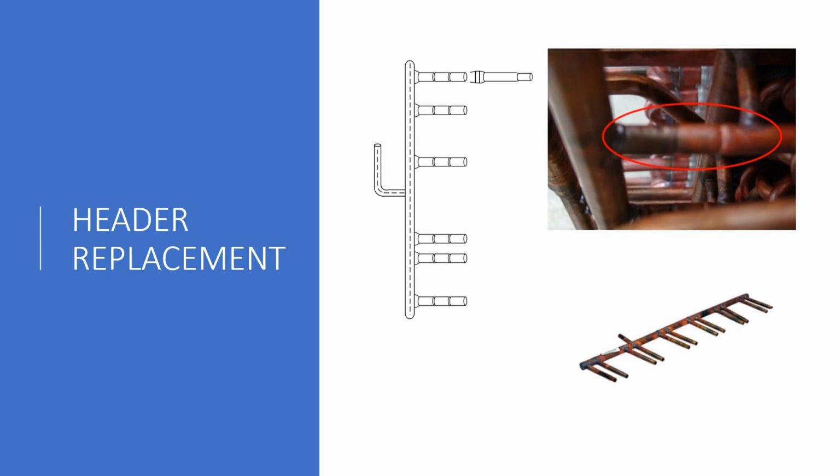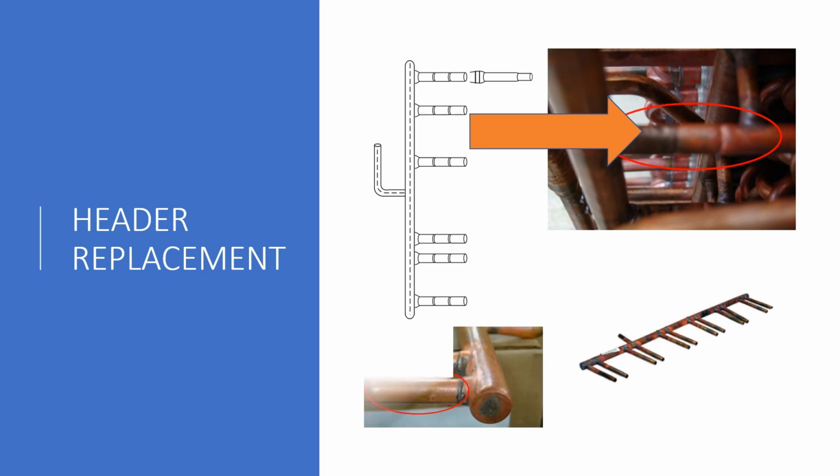AccuRaters are pistons that are inserted in the tubing coming off the header going into the coil. Most older units had dimples on either side of the location of the piston. A lot of the newer models have a stamp to show the location of the piston.